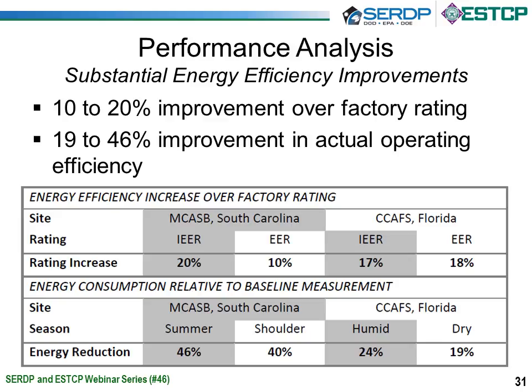Can you tell us if this technology is cost effective when you're only using it in one unit, or would this be mostly cost effective for larger scale applications? That's going to depend on whether it's a field retrofit or an installation on a new unit. If it's a new unit, definitely one piece of equipment will certainly have good economics. If it is a field retrofit, it really needs to be a larger unit to generate enough savings to cover all of the field costs. Doing work like this in the field is pretty expensive and it's very intense.